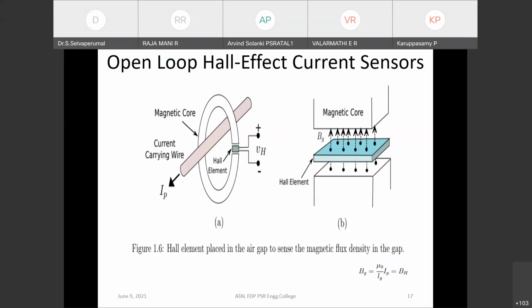Also, the very high permeability of the core keeps the magnetic flux confined within itself and the air gap only, right? So if the air gap is very small, the position of the current carrying wire in the empty inner space of the core does not affect the flux distribution significantly, and hence the expression of Bg holds, right? This fact can be utilized to build a clamp-on current sensor, which is very convenient for monitoring currents in industrial applications. Okay. Next slide.